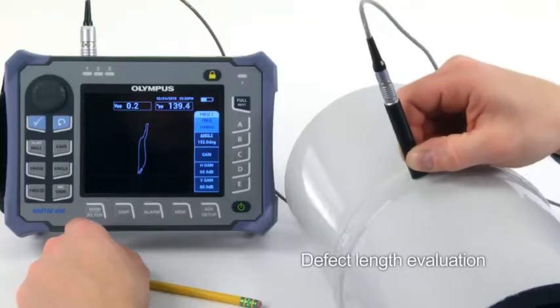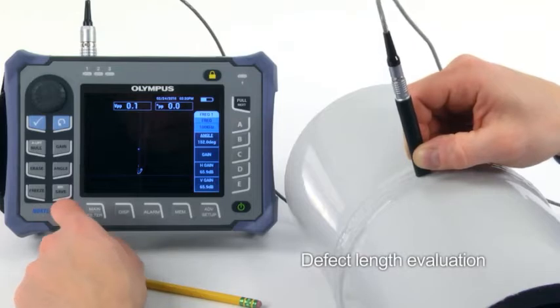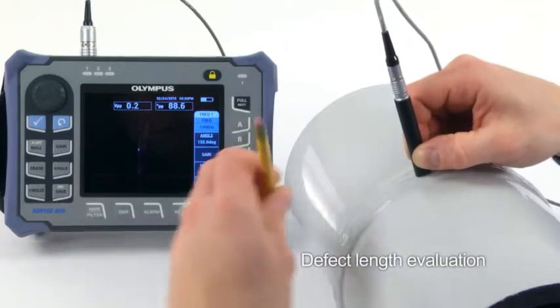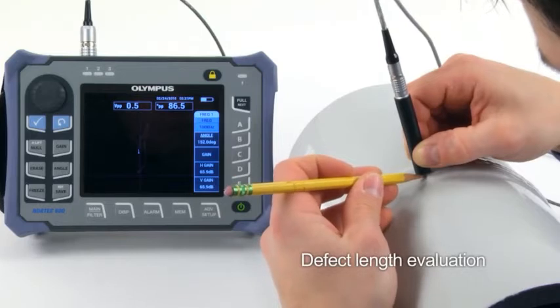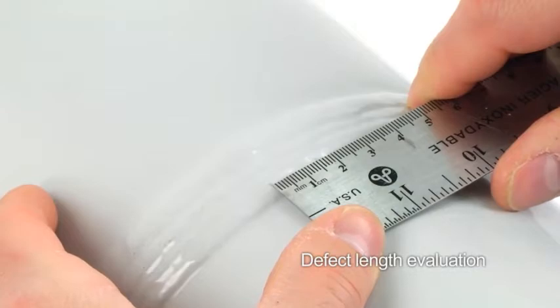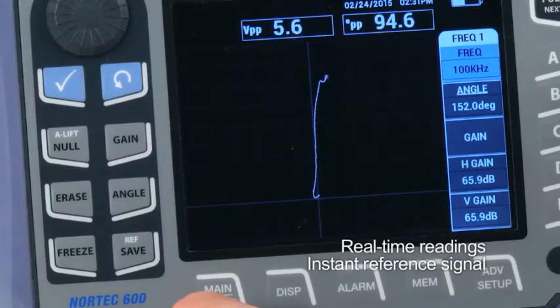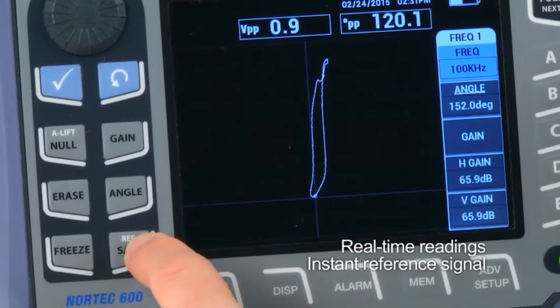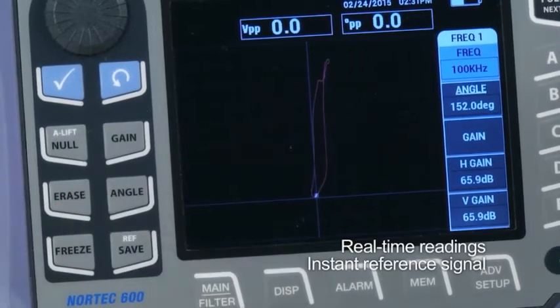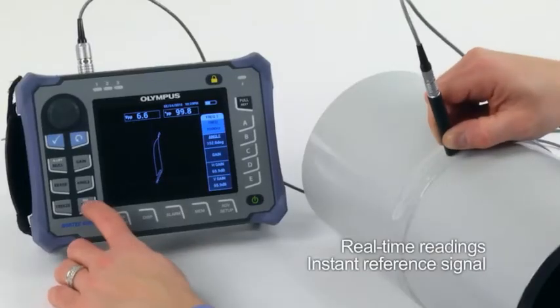The Nortec 600 weld inspection solution also enables defect length evaluation. The length can be estimated based on the -6 dB threshold on each side of the flaw. The combination of the Nortec 600 real-time readings and instant reference signal makes estimating an indication's length extremely easy.